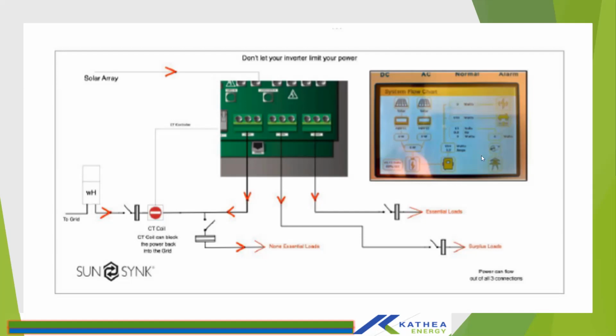So this is how the screen looks. It has a system flow chart where you can actually see the flow of power: how much power is coming from PV, how much is going to the battery, and how it is distributed to the loads. If you are feeding back to the grid, the CT meter will read a negative power to show that power is flowing into the grid.